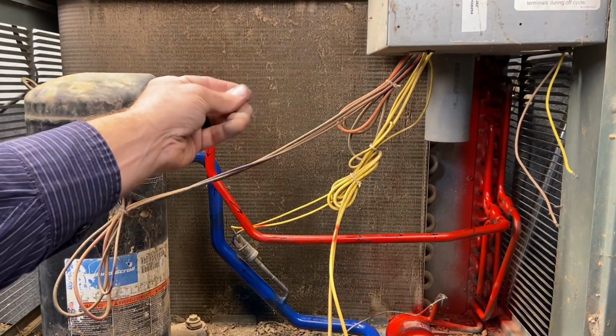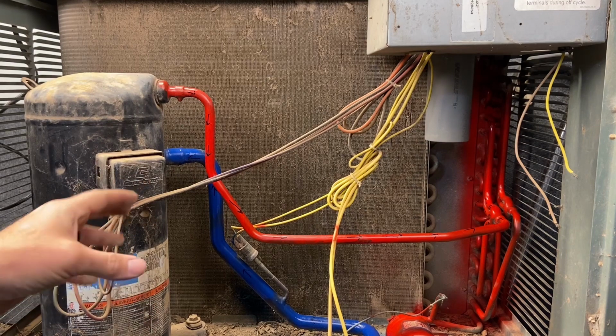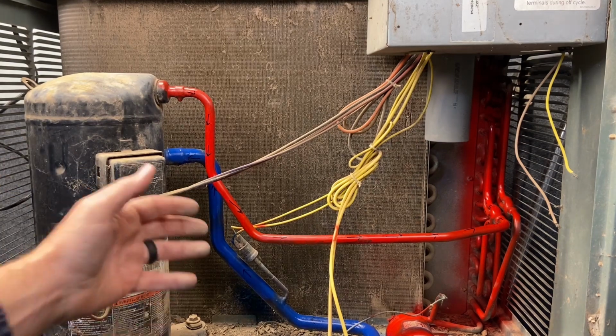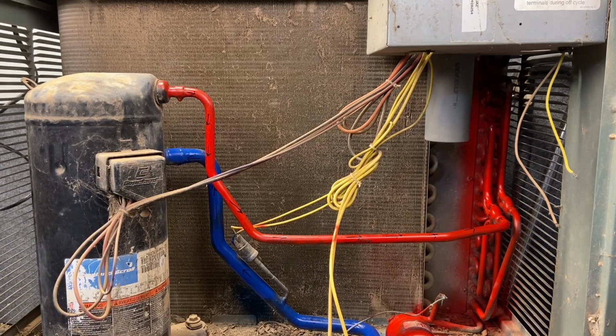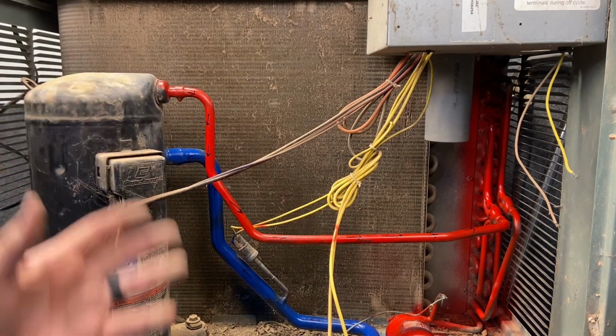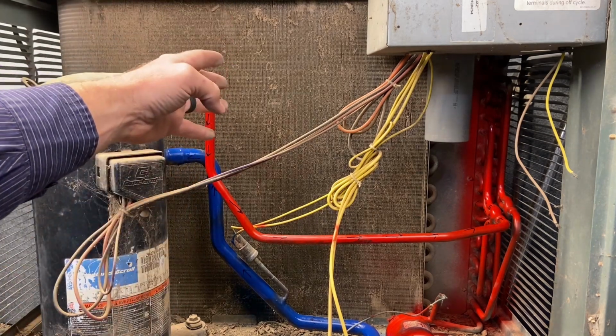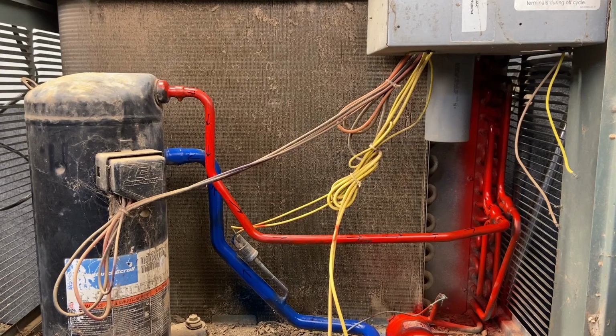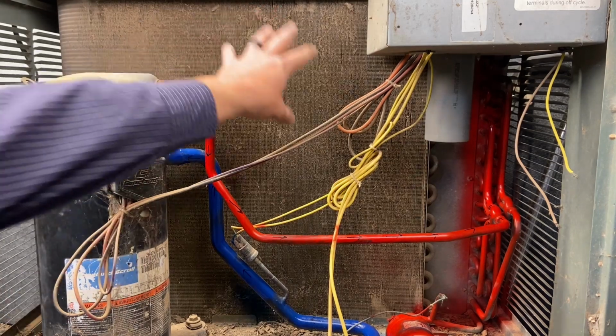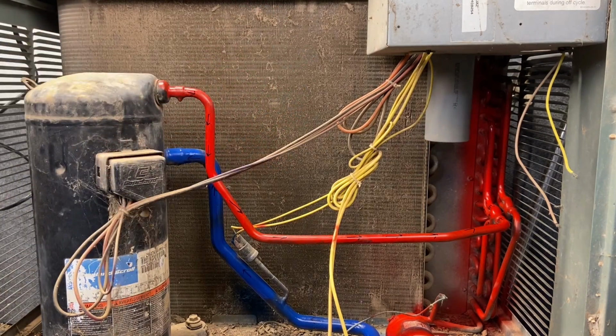We left these systems dirty so that we can clean them, and so that you know when you're working in HVAC, you're going to be dealing with all kinds of dirt and stuff. We're going to have to clean these up to keep the efficiency up. Dirt is a great insulator, and it slows the second law of thermodynamics. So with this dirt being on here, we don't transfer the heat like we need to.